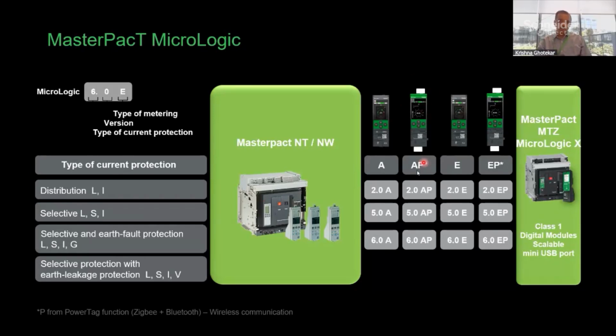So which means, let's say, if you want to have a communication as per the specs, like a communicable circuit breaker to communicate the trip unit parameters or the maintenance history or so on, or the contact wear and tear, as of today, you have to put a COM port, a BCM behind the trip unit, connect with the cable, then again add an IFM module, give a power supply to everything, and so on. Whereas in MTZ Active, you can directly have a different type of trip unit called AP or EP.